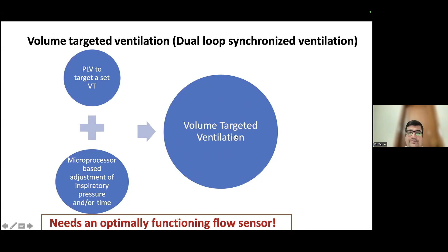I'm again going to repeat. The microprocessor tries to see what the difference is between the set tidal volume and the delivered tidal volume, and based upon this analysis, it will make subsequent adjustments in the next breaths in inspiratory pressure or time, so that the tidal volume delivered in the next breath matches the set tidal volume. Obviously, for optimal functioning of this mode of ventilation, you require an optimally functioning flow sensor.